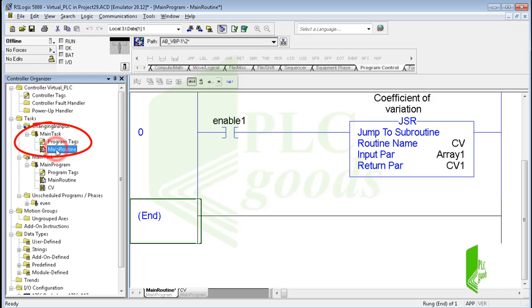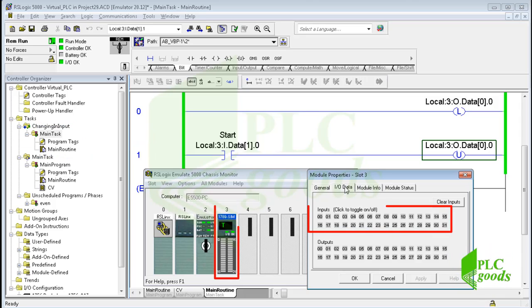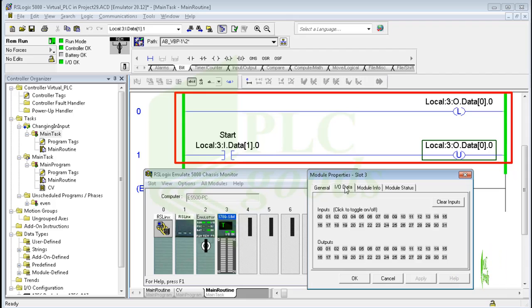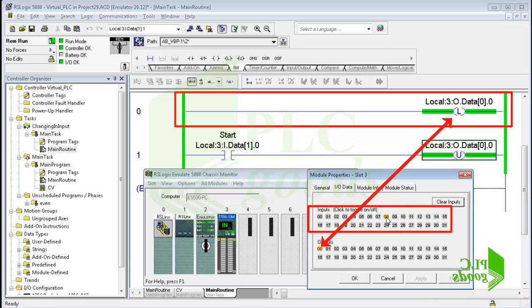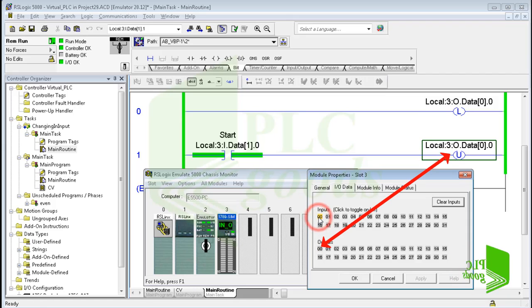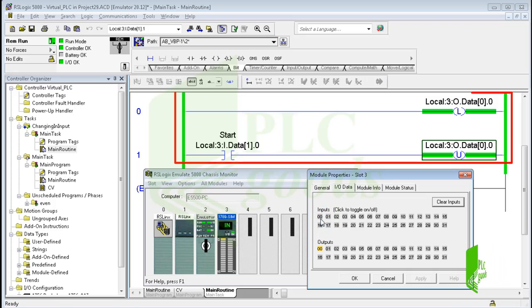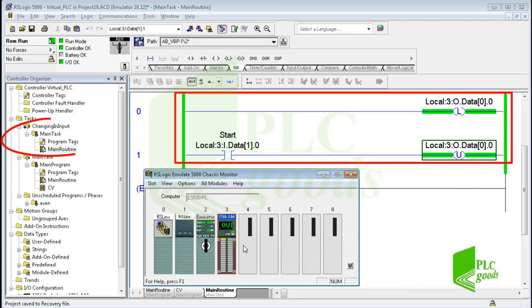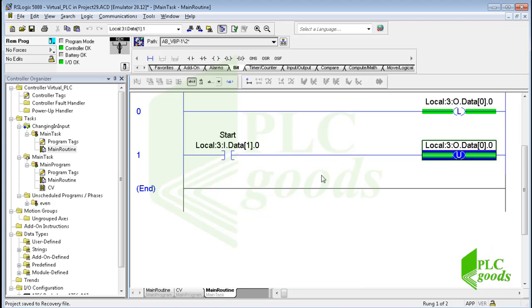Inside this routine I write a simple program and transfer it to the virtual controller. If I change any input address of the input/output module, this program will be executed. Based on the first rung, if I change any input address, the first digital output will turn on; but if the first digital input is activated, the controller will turn off the digital output. The main point is that the controller doesn't execute this program continuously — it executes this task only if it detects any changes at the input addresses of the module.